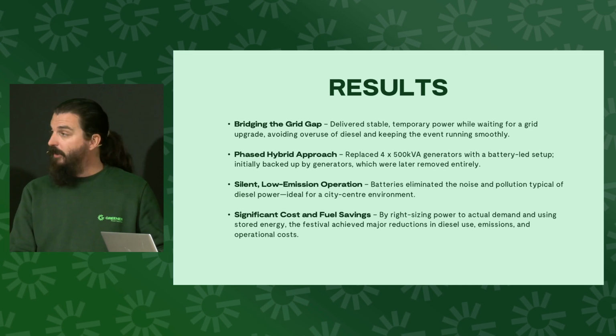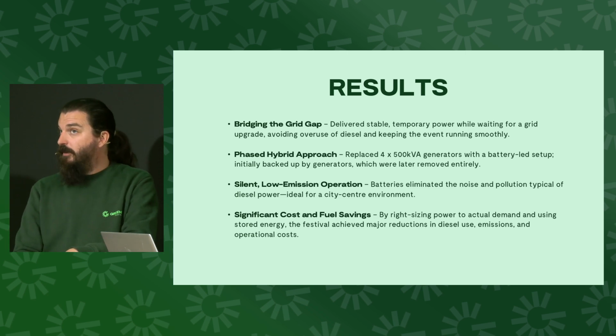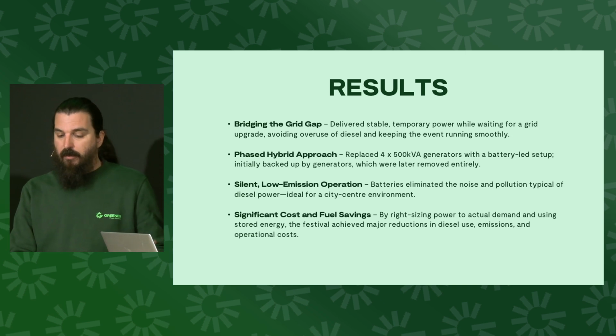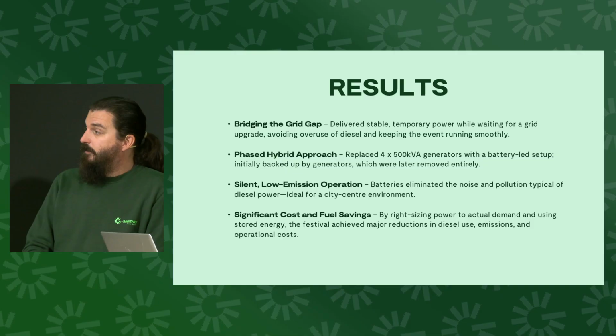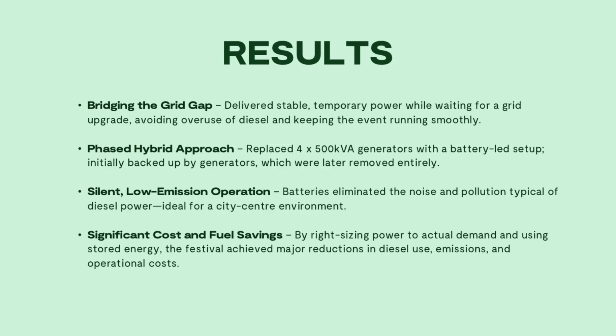So we did bridge the gap. We were able to help them bridge the time between the deliverance of the extra power from the grid, and by using a hybridized approach, we could utilize the grid fully until the capacity of the batteries was depleted, and then for the year after we could put in more capacity. And if the customer did want some resilience on site still, because of course how they're running now is the 400 amp connection supplying everything, there is no resilience or backup in there. However, if they did want that, we can put it all back again. Batteries back in again. So that's all going to costs and savings, right? Of course, which is what we try to endeavour.